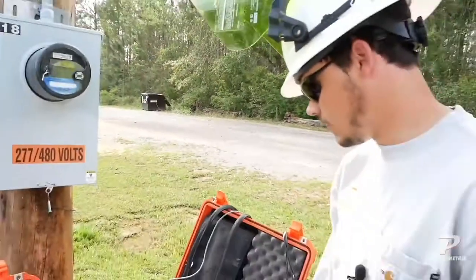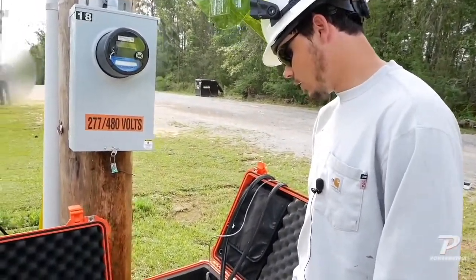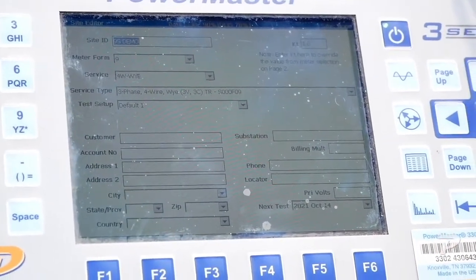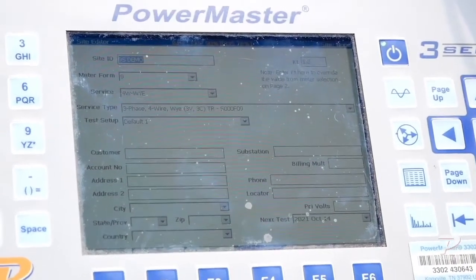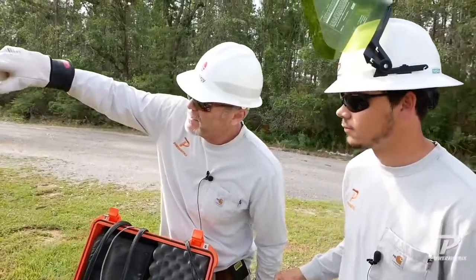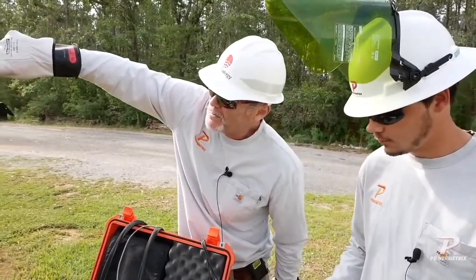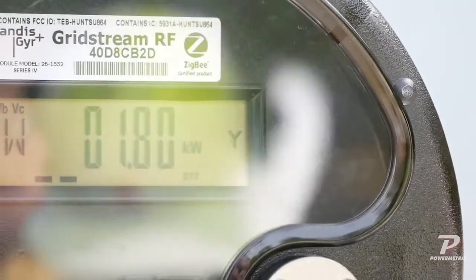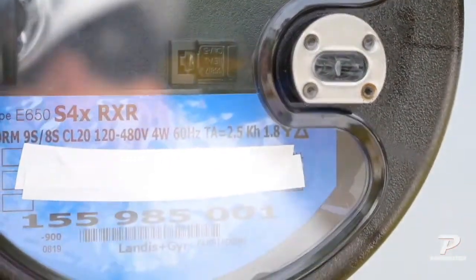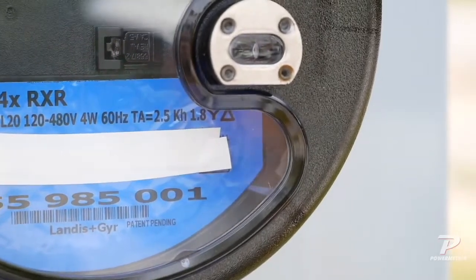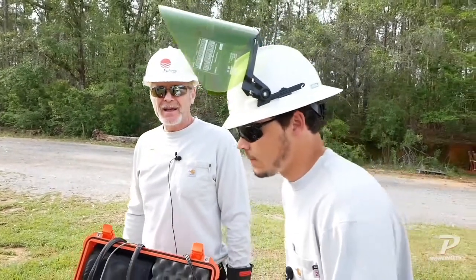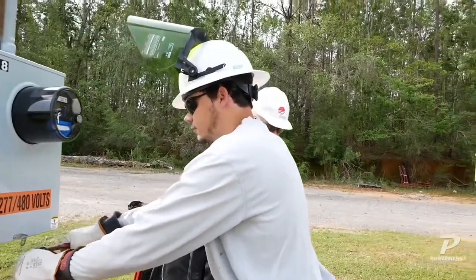Information comes from, and I've got it in here, set up, ready to rock and roll. So did y'all catch what he was saying? You looked up there and you saw that it was a Y on the screen like we've been talking about, right? And it also says it on the face right there. It's telling you it's at 1.8, which is typical of your 9S meters. So we've noticed that up there that it is a Y. If it was a delta, it could be an 8, but this is a Y, so it is a 9.